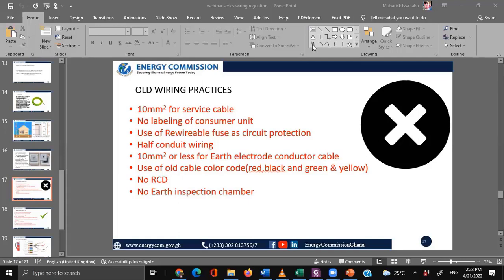Then the use of rewireable fuse, that's circuit protection. A fuse isn't a bad protective element, but there's a better protection than that, which is the MCB. So using a fuse, yes, of course, when there's a fault, it responds and blows out. But once it blows out, you have to wait for a professional to come and rewire the fuse, or you have to buy a new fuse altogether, which is quite tiring. But the MCB doesn't present that to you. The MCB will trip for as long as the fault persists, but once it's cleared, that is it. You can switch your MCB back on and enjoy your power.